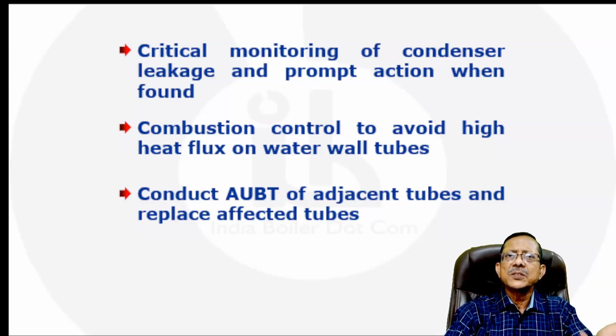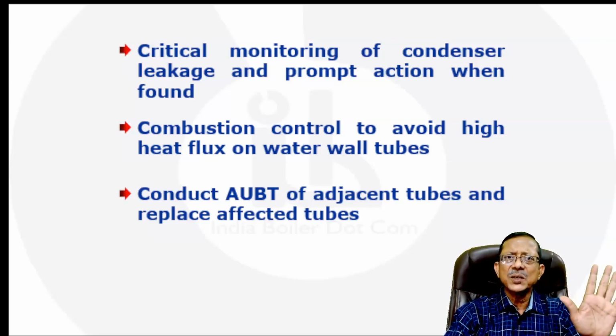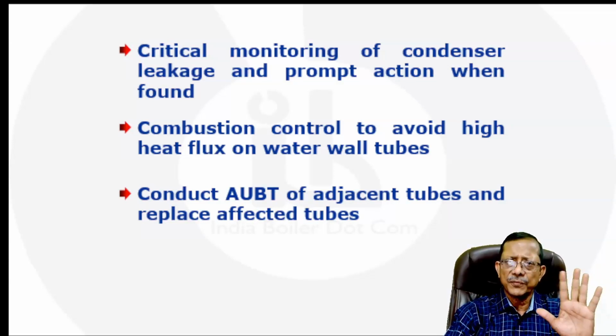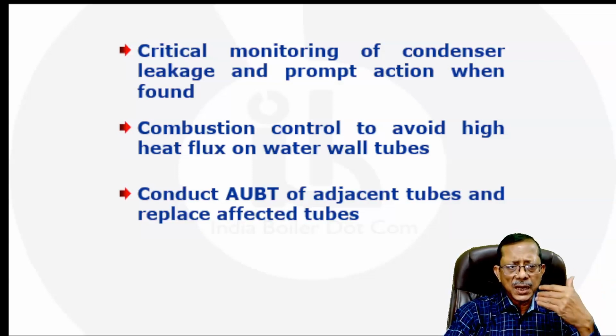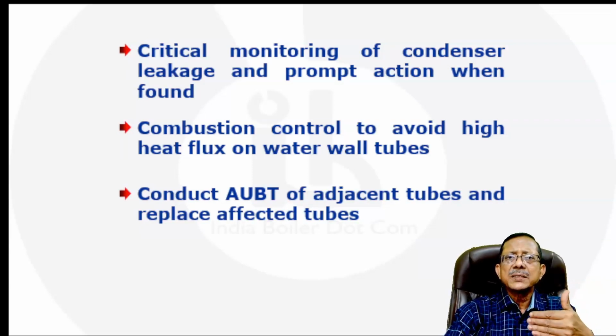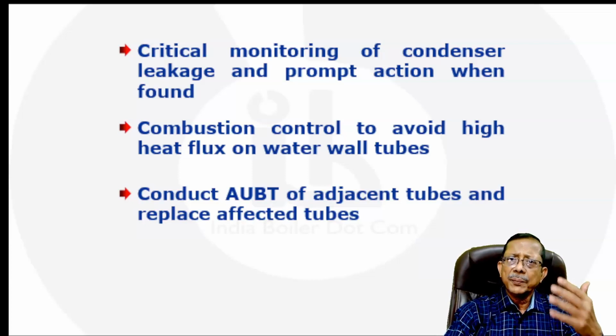That is basically an advanced ultrasonic backscatter test mechanism, which is going to identify whether micro cracks are there on the components. And when you identify them, replace the tubes to prevent further failure, right? So these are the things you should take as a precautionary measure right before the failure occurs, because whenever such conditions are there in the system, it may lead to a failure like a hydrogen embrittlement failure in your system.